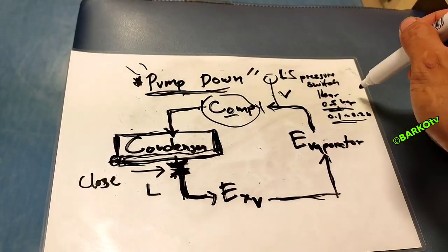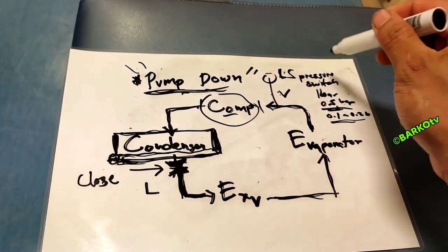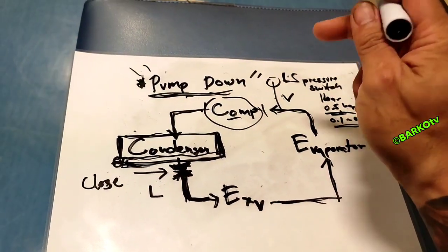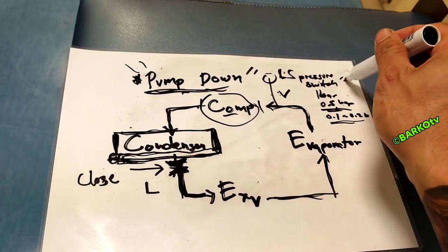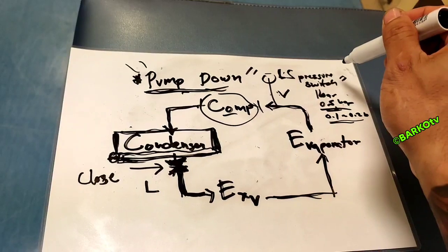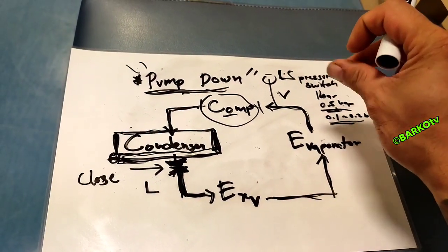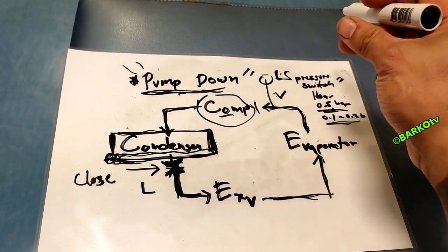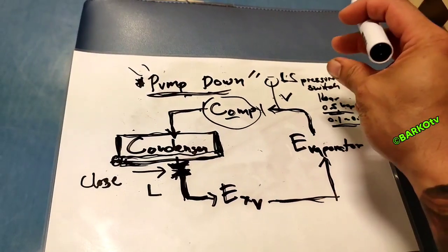To recap: this is the manual pump-down procedure. Simply close the isolation valve after the condenser to pump down your system and collect the refrigerant.